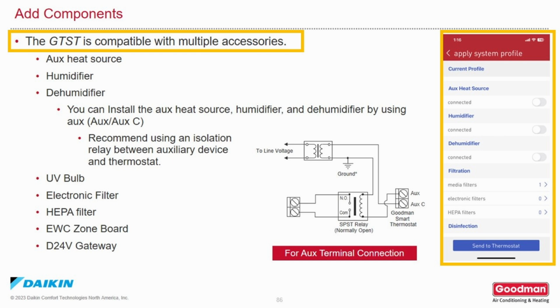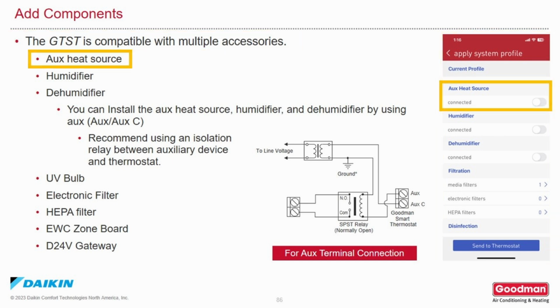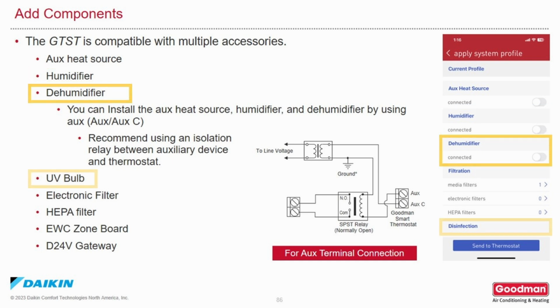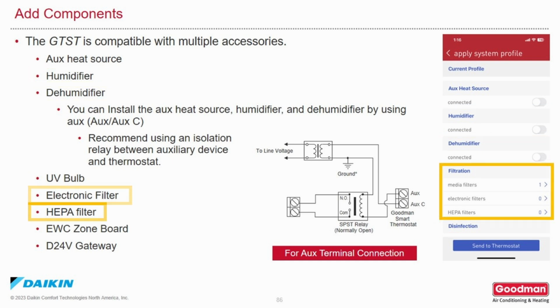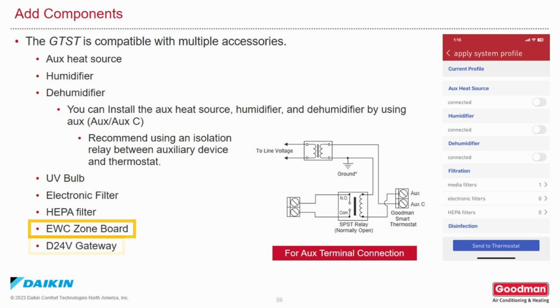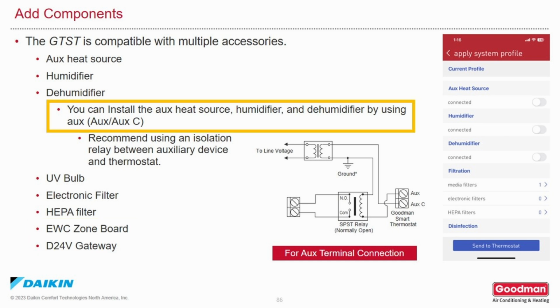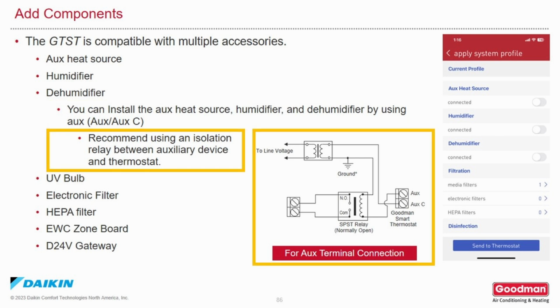The GTST Smart Thermostat is compatible with multiple accessories such as auxiliary heat sources, humidifier, dehumidifier, UV light, electronic air filter, HEPA filter, EWC zone board, or the D24-volt gateway. You can install an auxiliary heat source, humidifier, or dehumidifier by using the auxiliary and auxiliary C terminals. However, it is recommended that you use an isolation relay between the auxiliary device and the thermostat, such as a single-pole, single-throw relay that's normally open.